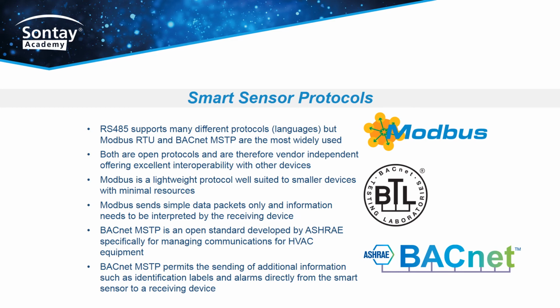Smart sensor protocols. RS485 supports many different protocols, but Modbus RTU and BACnet MSTP are the most widely used. Both are open protocols and are therefore vendor independent, offering excellent interoperability with other devices. Modbus is a lightweight protocol well suited to smaller devices with minimal resources. Modbus sends simple data packets only, and information needs to be interpreted by the receiving device.